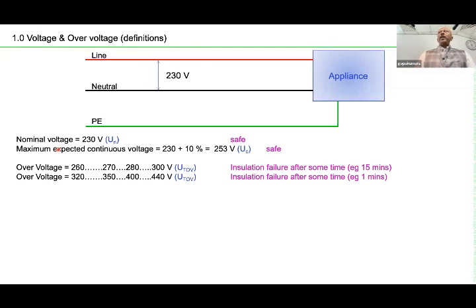For example, for the duration, let's say 270 volt for 15 minutes, there can be a chance of failure. Similarly, with a voltage even more than 300, 320, the failure will be much faster, because the voltage is even more. The withstanding time will be very small, because more current flows through the conductors.